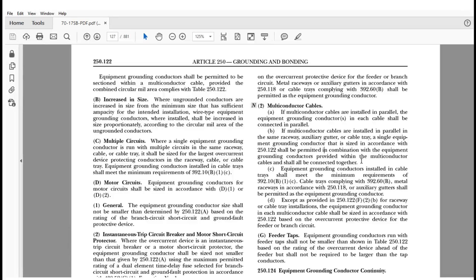So this gives you some ability here, depending on your application, whether or not you're installing them in a cable tray, in a raceway, or an auxiliary gutter. This does give you some leeway here. Now, it goes on to bring in another one here. It says C, equipment grounding conductors installed in cable trays. Okay, so it's bringing some more info here. Remember, we're still talking about multi-conductor cables. It says equipment grounding conductors installed in cable trays shall meet the minimum requirements of 392.10(B)(1)(c).